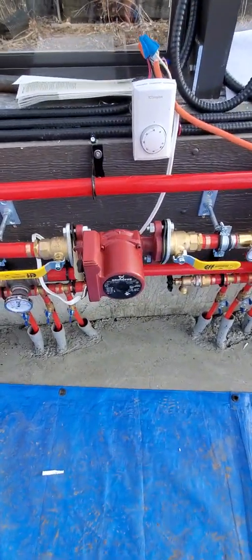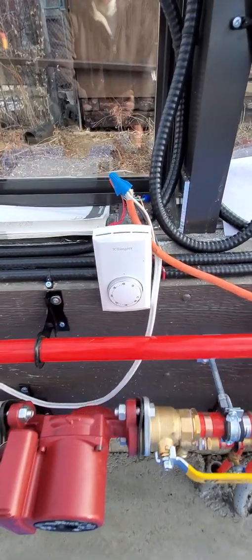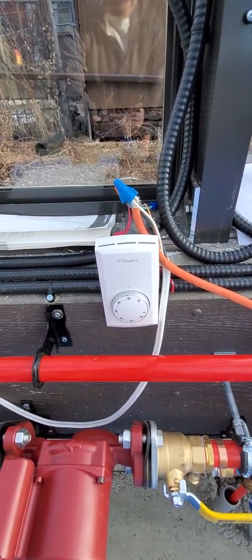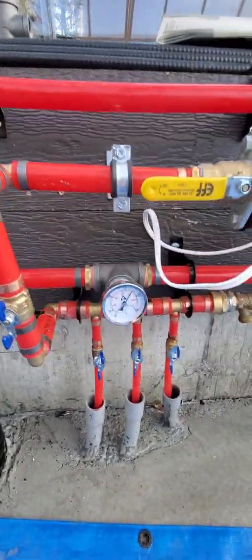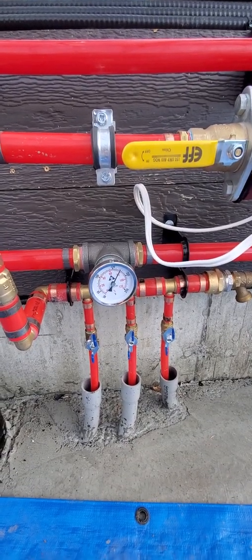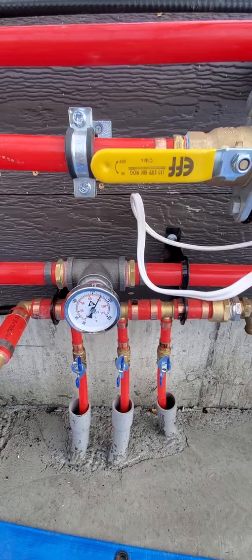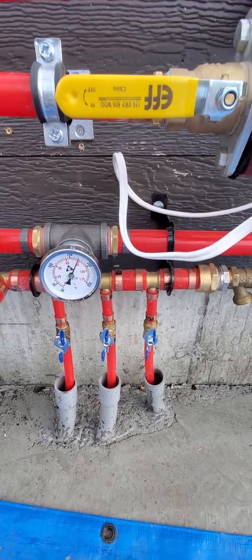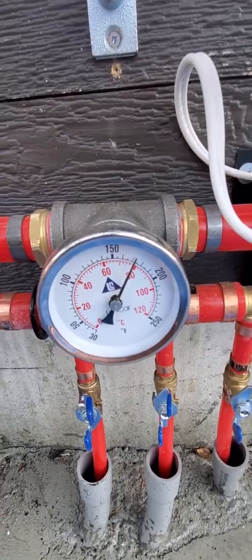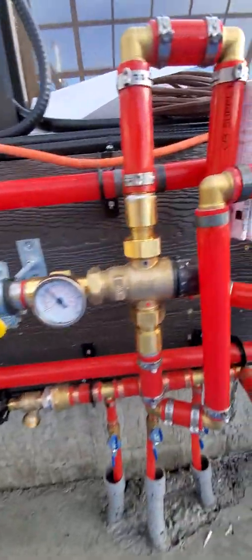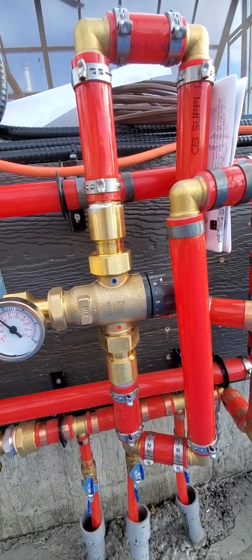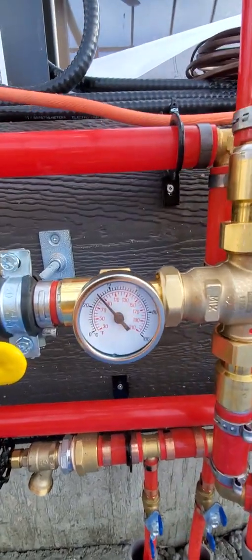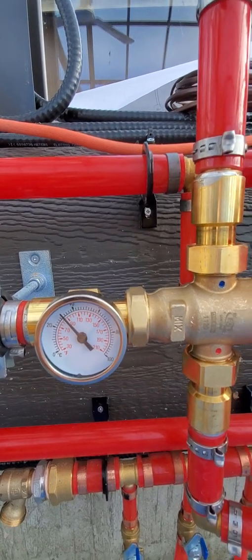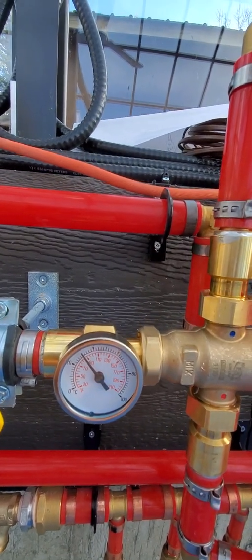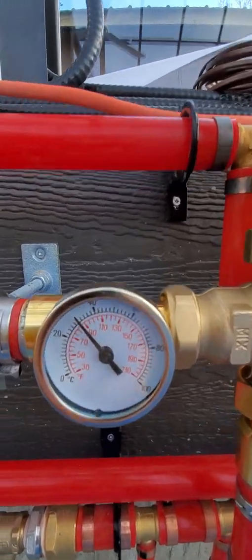I've got a small pump here that'll click on when the temperature goes to anything that's below 10. And right now, you can see it is 80 degrees Celsius, or about 170 or so Fahrenheit. And then you can see I have a mixing valve here to make sure it doesn't run wild and get too hot on the floor. And you can see we're going into the floor at about 90 degrees Fahrenheit and 30 degrees Celsius.